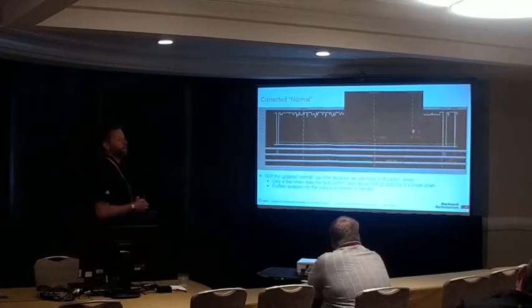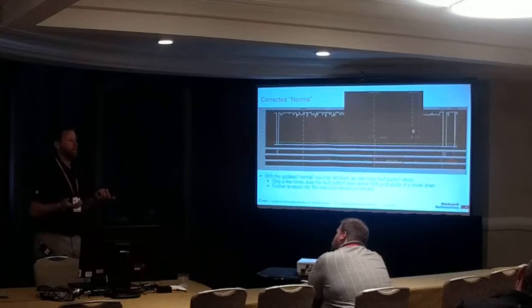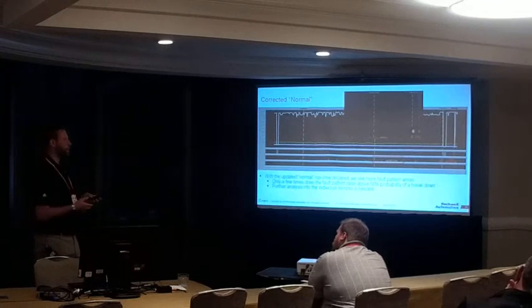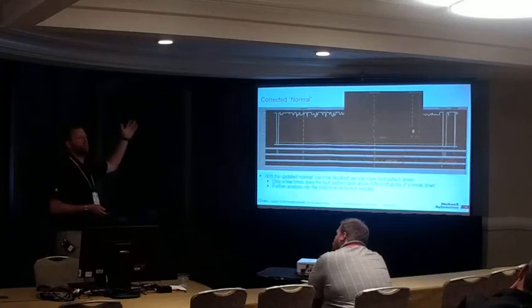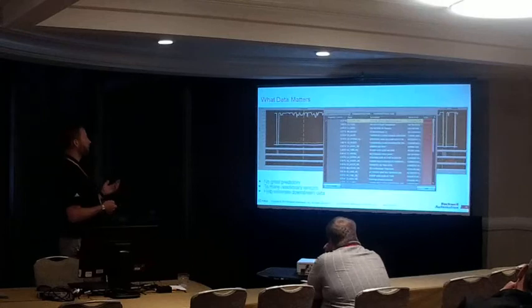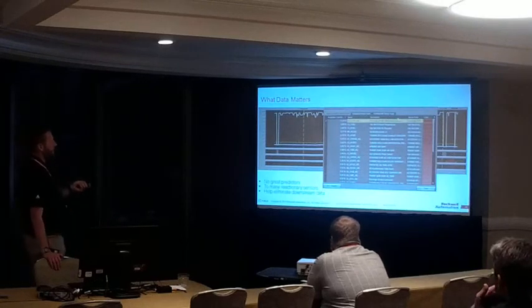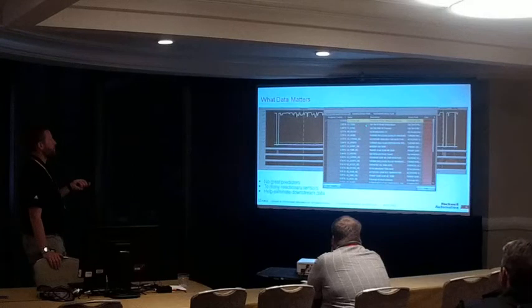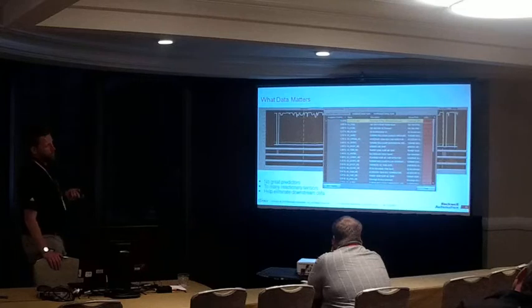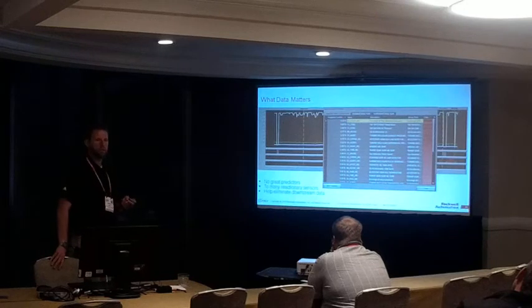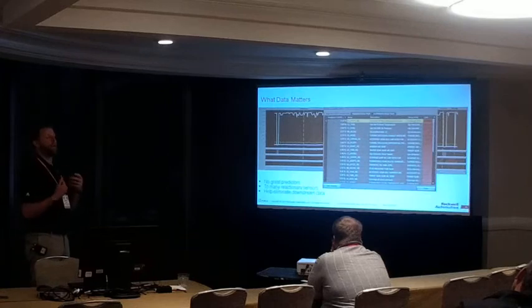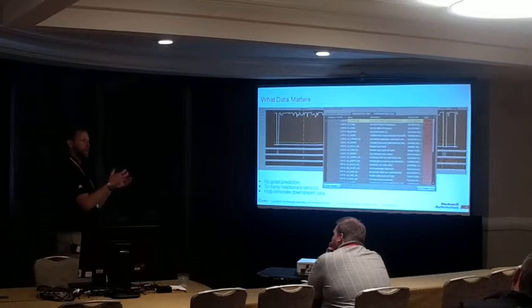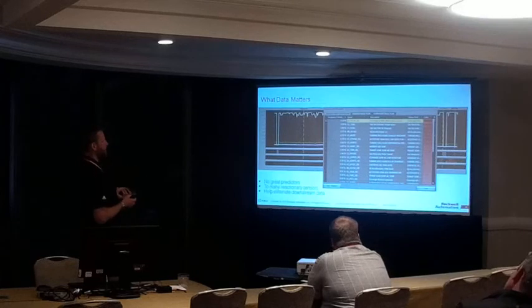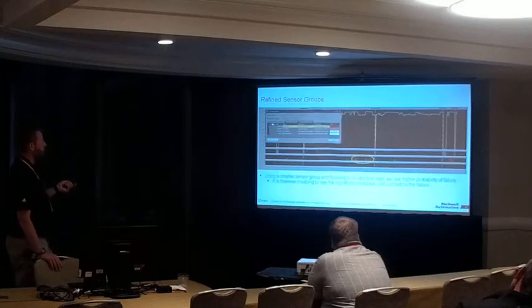But now, keep in mind, we're also looking at all 32 data parameters. Those data parameters may not be relevant. The humidity sensor on one end of the machine may have no relevancy to the bearing. So then we look at all the data tags that we have, and we see, well, even the one that's the differential pressure, the one that's most contributing to this failure prediction is less than 5% correlation. So we say, all right, we need to do some refinement. We're going to eliminate some of these sensors from our analysis in this particular case and see if we can get a better prediction. So in this case, we ended up narrowing it down to 4 specific parameters.